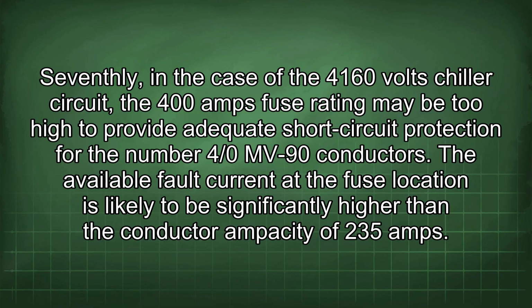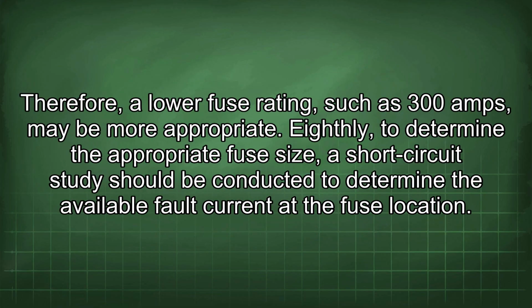Seventhly, in the case of the 4160 volts chiller circuit, the 400 amps fuse rating may be too high to provide adequate short-circuit protection for the number 4/0 MV-90 conductors. The available fault current at the fuse location is likely to be significantly higher than the conductor ampacity of 235 amps. Therefore, a lower fuse rating, such as 300 amps, may be more appropriate.